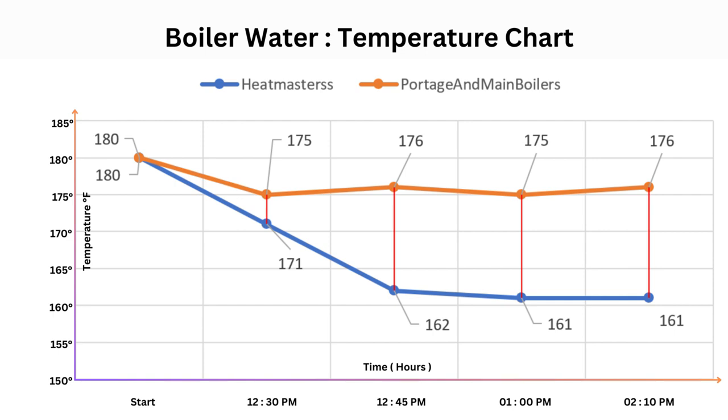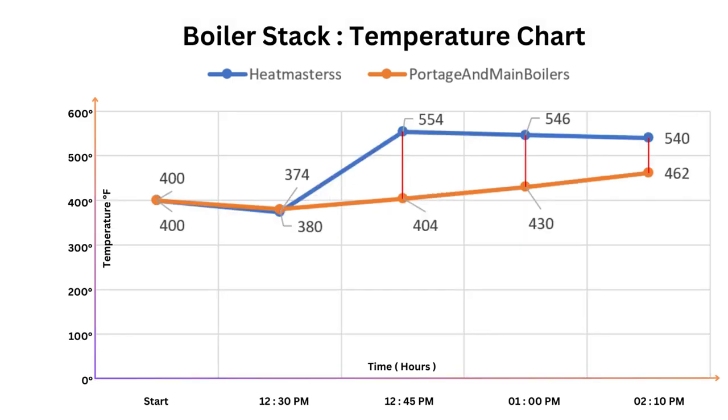Based on the numbers we're seeing, we're going to unplug one heater on each boiler to make the test more fair. The Heatmaster is only delivering 161-degree water to the two unit heaters and falling behind, while the PortageAndMain is delivering 176-degree water. The stack temperatures are 429 degrees for the PortageAndMain and 546 degrees for the Heatmaster — and as the fire works harder to catch up, that stack temperature may climb even higher.